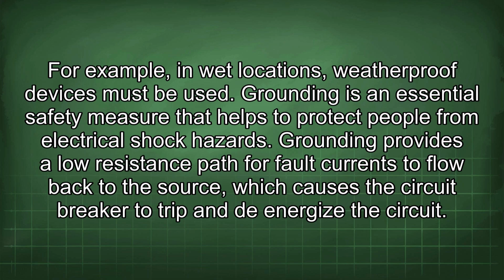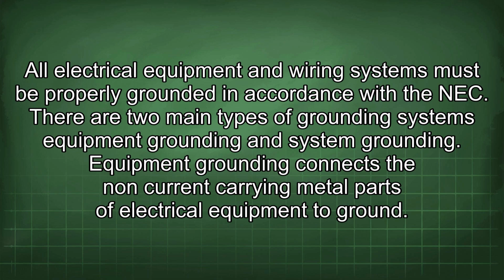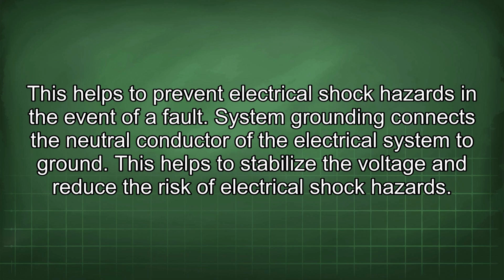Grounding is an essential safety measure that helps to protect people from electrical shock hazards. Grounding provides a low resistance path for fault currents to flow back to the source, which causes the circuit breaker to trip and de-energize the circuit. All electrical equipment and wiring systems must be properly grounded in accordance with the NEC. There are two main types of grounding systems: equipment grounding and system grounding. Equipment grounding connects the non-current carrying metal parts of electrical equipment to ground. This helps to prevent electrical shock hazards in the event of a fault. System grounding connects the neutral conductor of the electrical system to ground. This helps to stabilize the voltage and reduce the risk of electrical shock hazards.